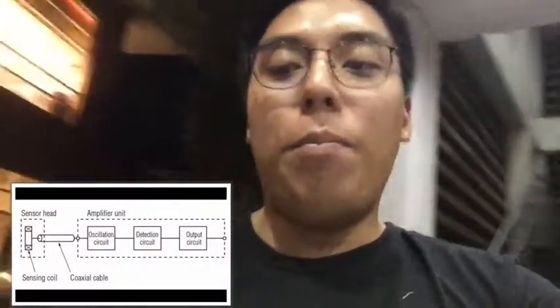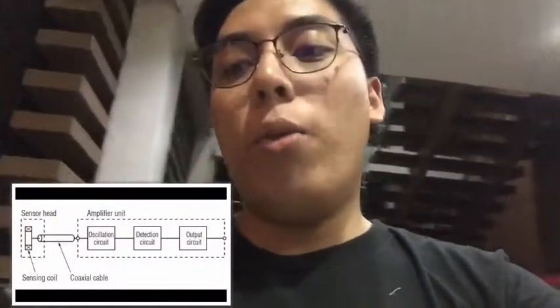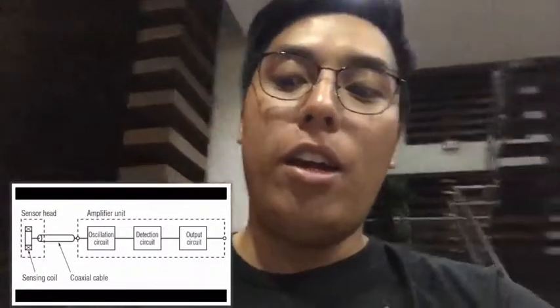There are two types of classification of inductive sensors. First classification, we have the self-contained type. The sensor can be used as soon as the power is turned on. Sensitivity adjustment is not available. Next one is the separate amplifier type. It has a small sensor head. Wiring is required between the sensor head and the amplifier.